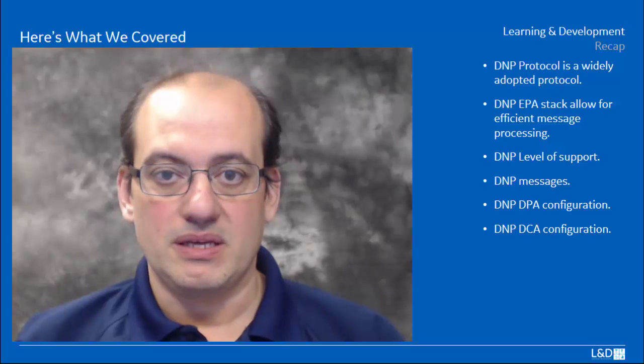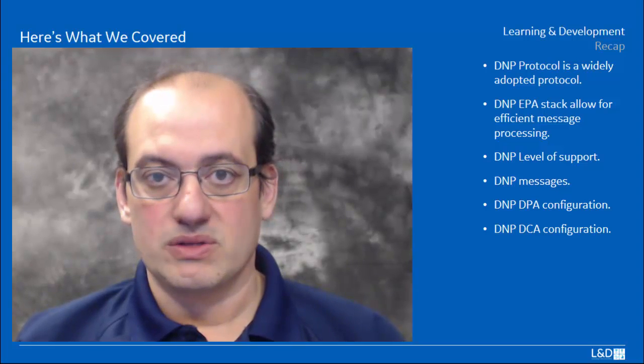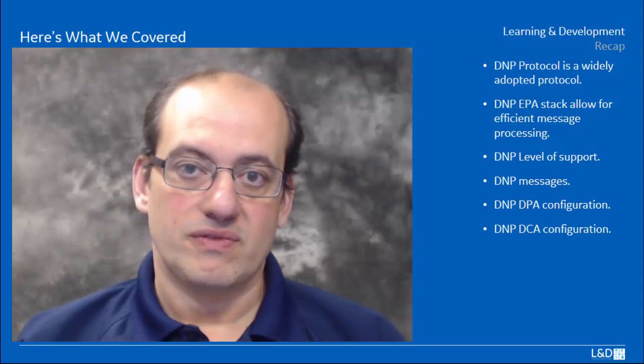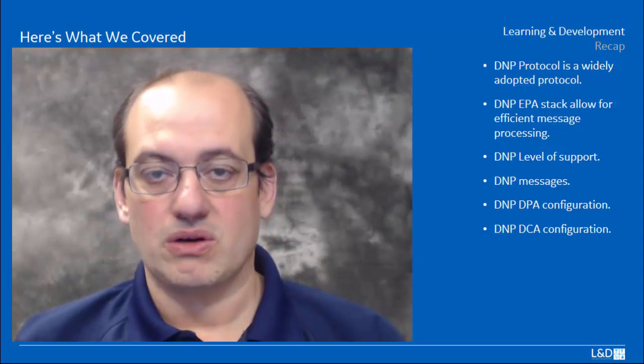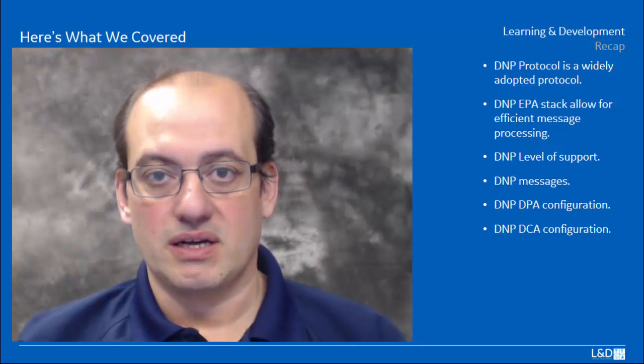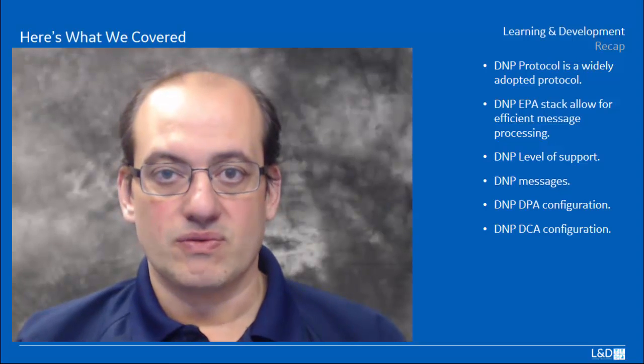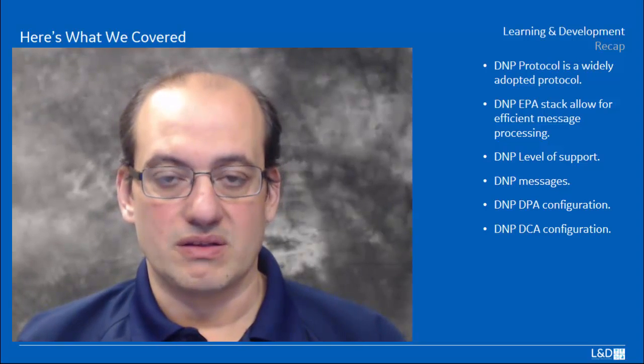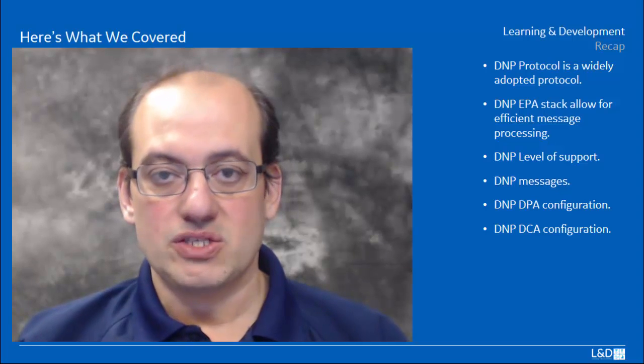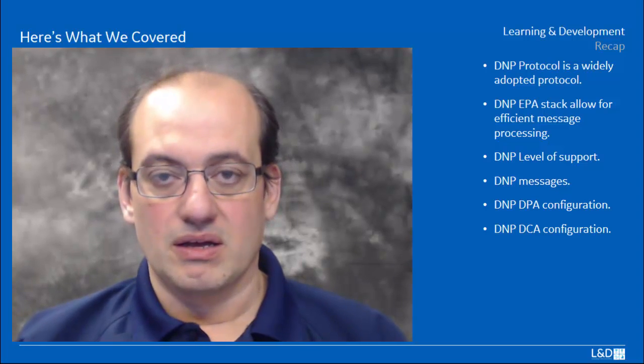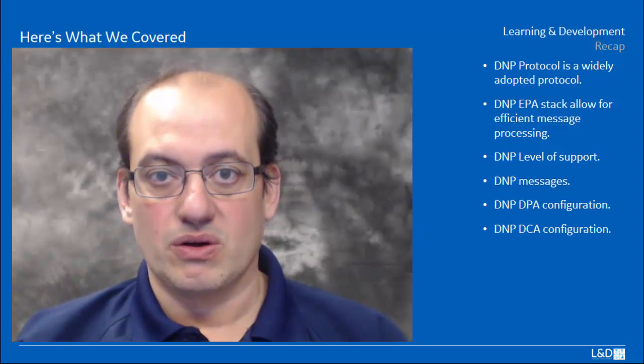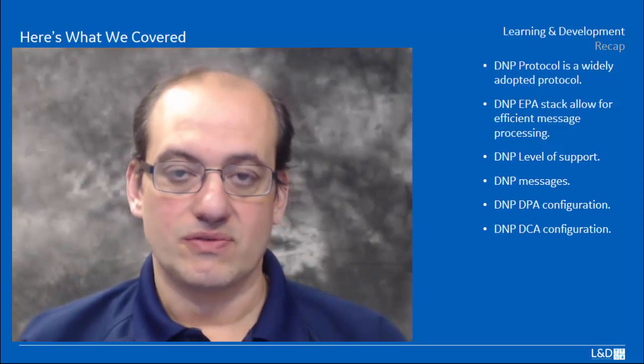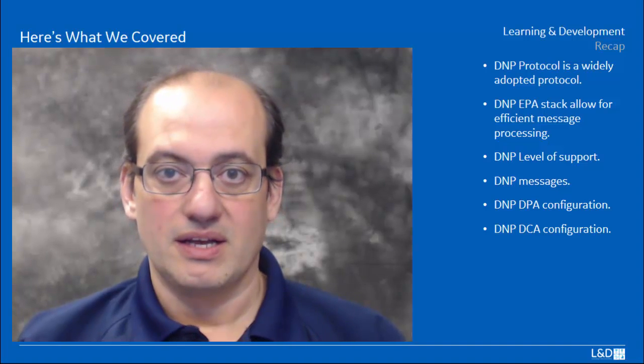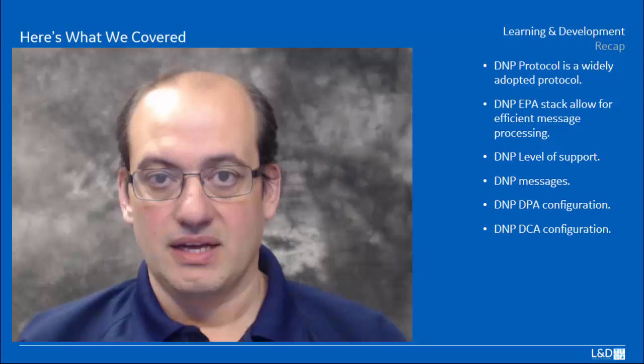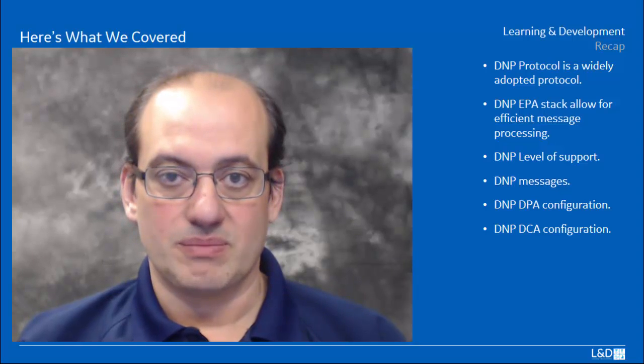And the DNP levels allowed flexibility for different vendors to implement a portion of the protocol and not be stringent to implement the entire protocol, from DNP level 1, 2, 3, and 4. The messages that were implemented pertained to each one of the stack layers: the data link layer, the physical layer, and the application layer part of the message.